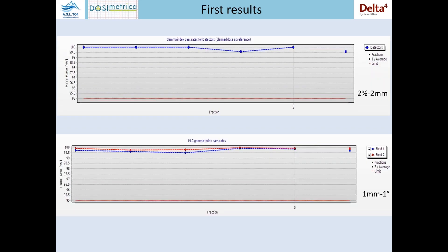The next graphs show the gamma index pass rates for the detectors — the 3D dose distribution gamma index pass rate. We used acceptance criteria of about 2% at 2 millimeters. In this case, the square point on the right is the mean value while the round points show the trend of each fraction. The last graph shows the MLC gamma index pass rate. Using one millimeter per one degree, there is a good passing rate for each fraction, and the mean value is about 99%.